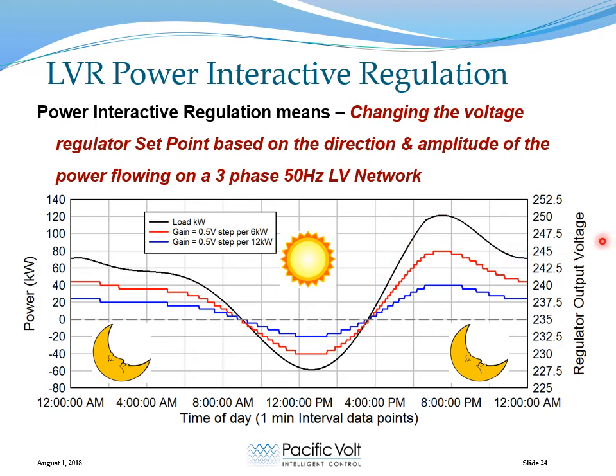What was going on in Australia is people would put in rooftop solar, and then they would think, well, we have this basically free energy source on our roof, so the next thing they would do is go out and install a larger air conditioning unit. So not only do they have a large amount of reverse power flow during the middle of the day, people come home at night and turn on their AC, and the peak load in the evening suddenly became 2 to, in some cases, 4 times what it had been historically and what the LV network feeder was designed to accommodate.